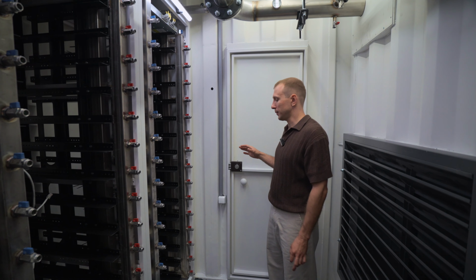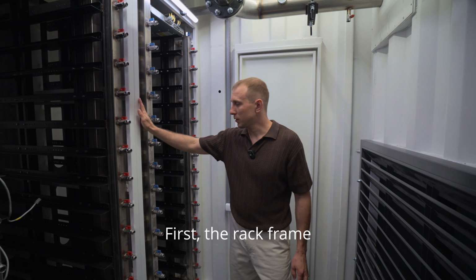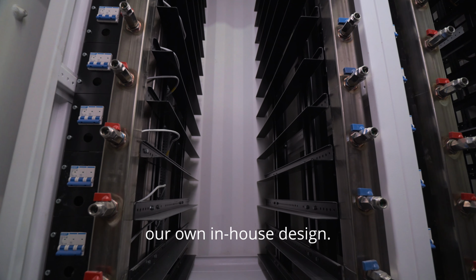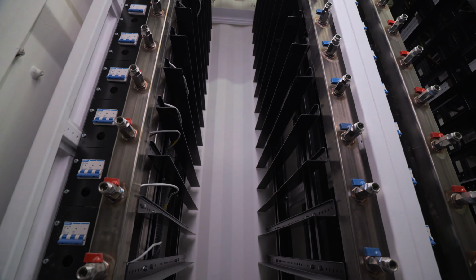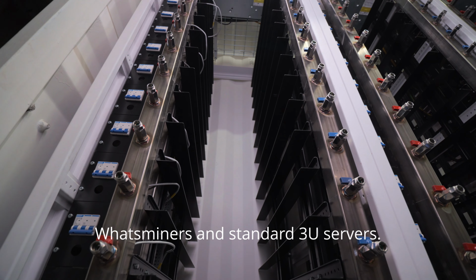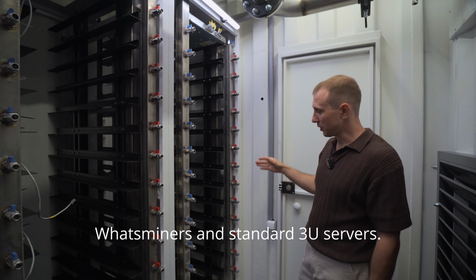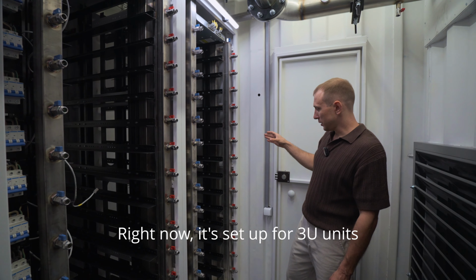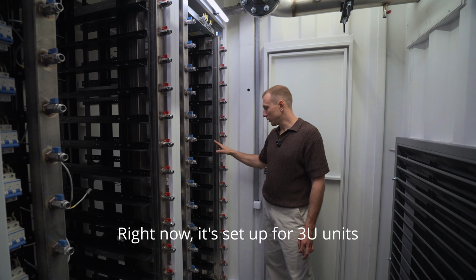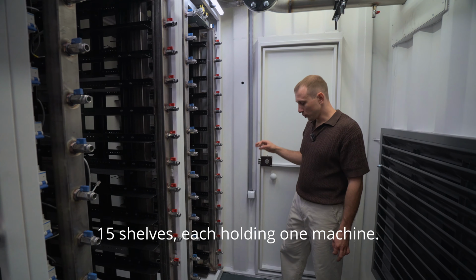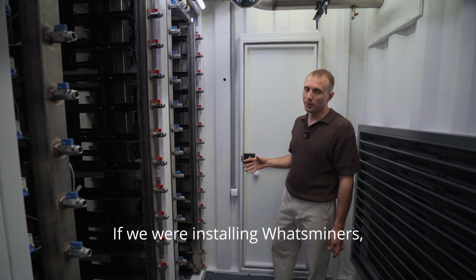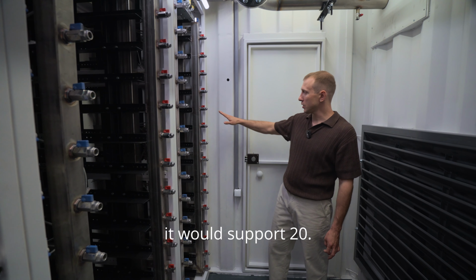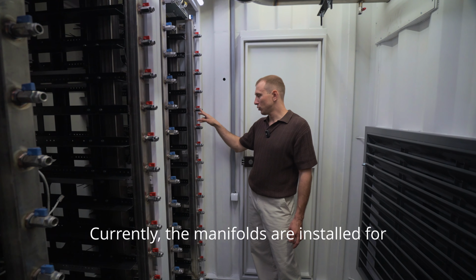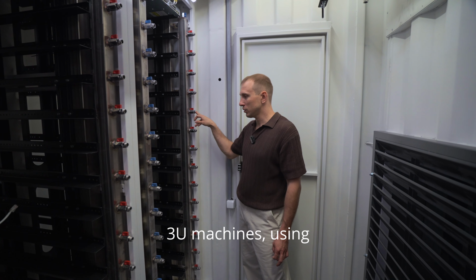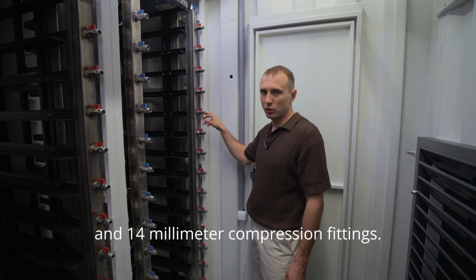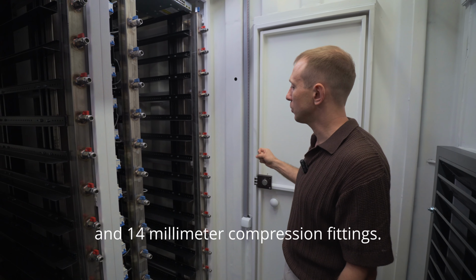The internal structure. First, the rack frame, our own in-house design. This frame can be configured for both Whatsminers and standard 3U servers. Right now, it's set up for 3U units, 15 shelves, each holding one machine. If we were installing Whatsminers, it would support 20. Currently, the manifolds are installed for 3U machines, using 3/4-inch connectors and 14mm compression fittings.